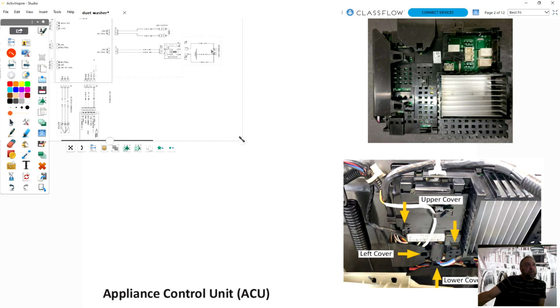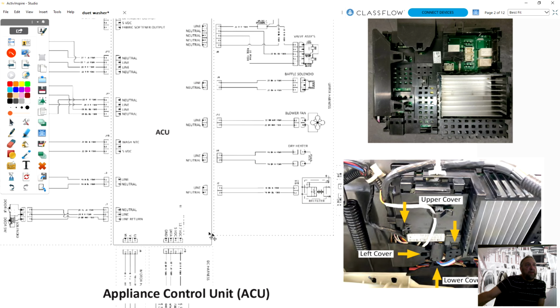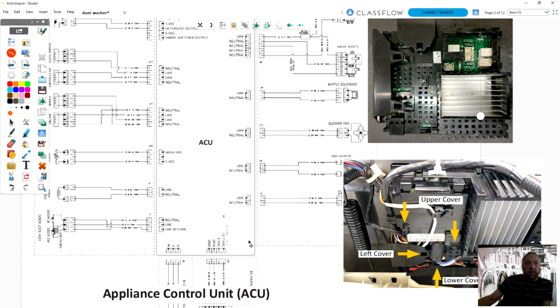Let's take a close-up look at this diagram and identify some things. I know it's a little blurry, I got clearer images as we go through, but you can see areas where it says line and neutral, line and neutral, line and neutral. That means all the components connected to the board at those plugs are 120 volt, getting line 1 and neutral directly. Like this blower fan right here, it's a 120 volt blower fan.